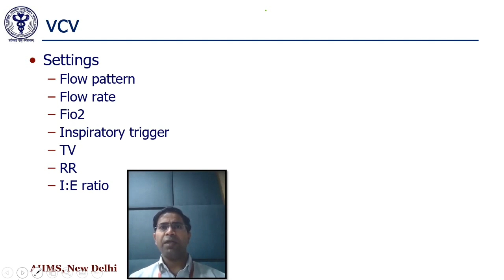Then we choose respiratory rate to achieve a desired minute ventilation. I to E ratio is kept on the basis of respiratory time constant, and respiratory time constant is the product of resistance and compliance. We have to keep the expiratory time minimum 3 times the respiratory time constant. In a few ventilators we can choose T-pause. For the T-pause, we keep a setting around 10 to 20% of the inspiratory time.